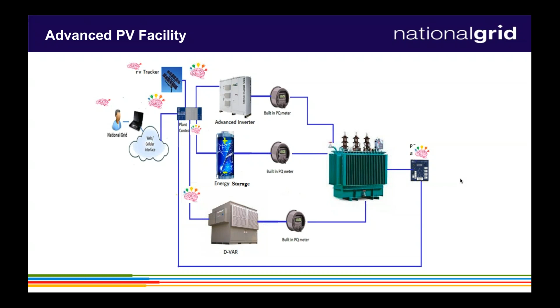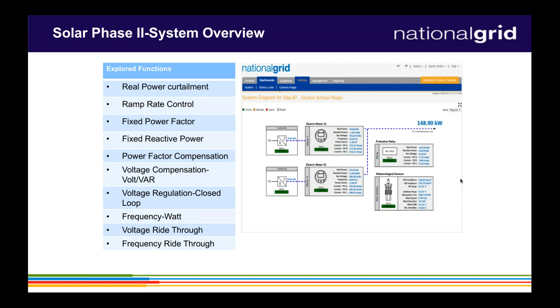So to us, you can have an advanced inverter, but that doesn't make it an advanced facility. And that plant master controller is a really important component of making that facility capable of really being a better steward of the grid. And the capabilities are listed. They are a lot of what you tend to expect when you hear advanced inverters. I won't read through them all, but the different curves and settings of those become a really important factor of the advanced inverter functions.